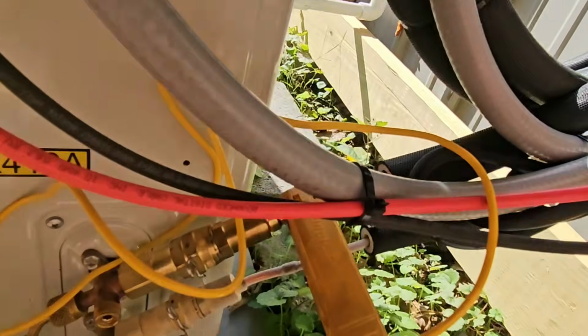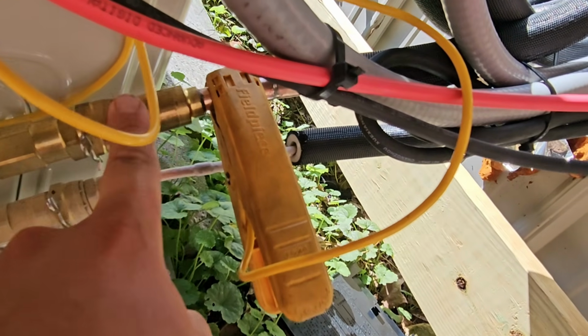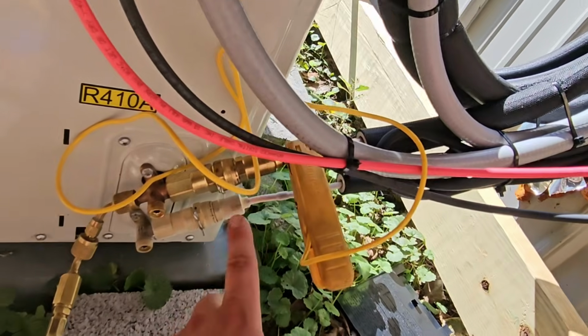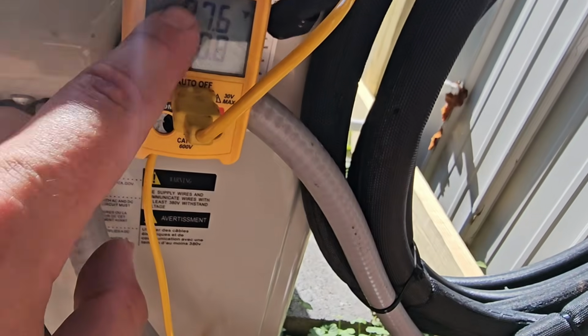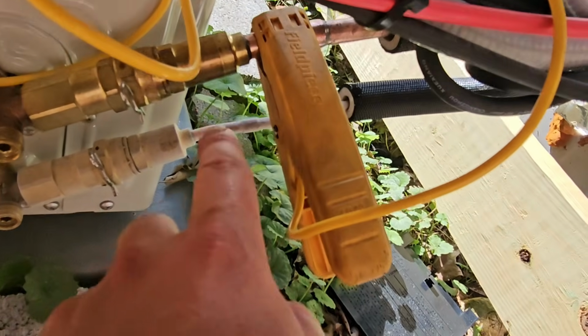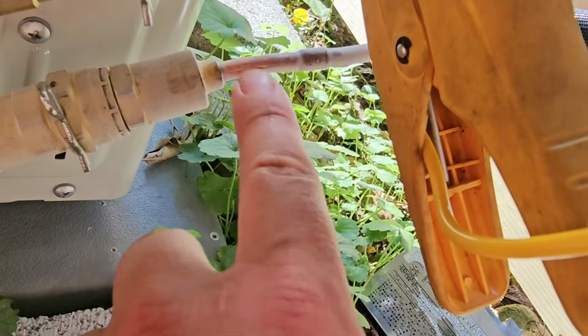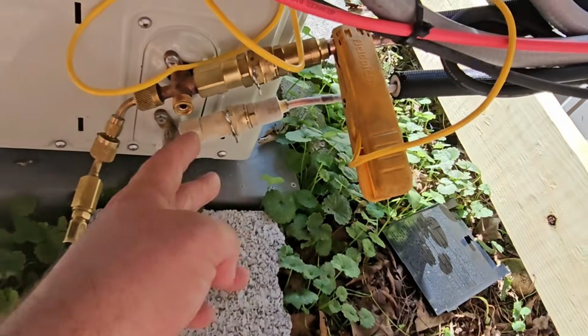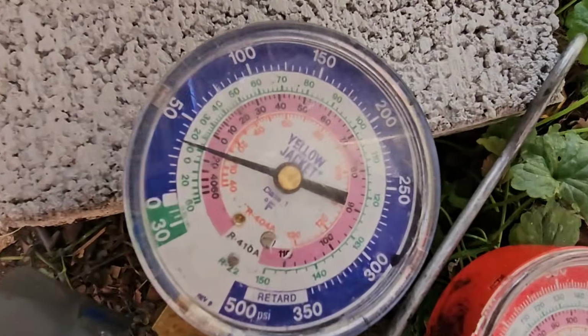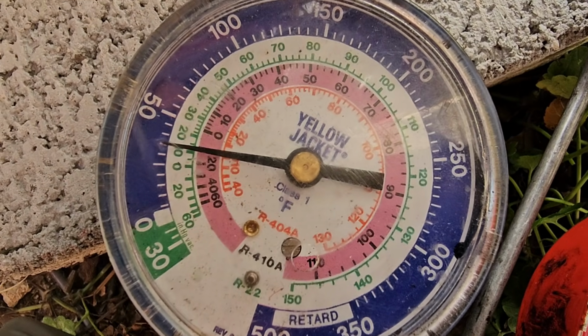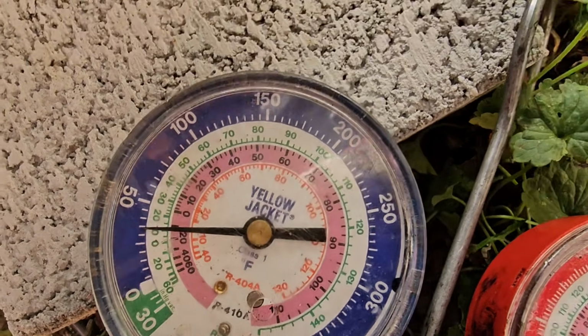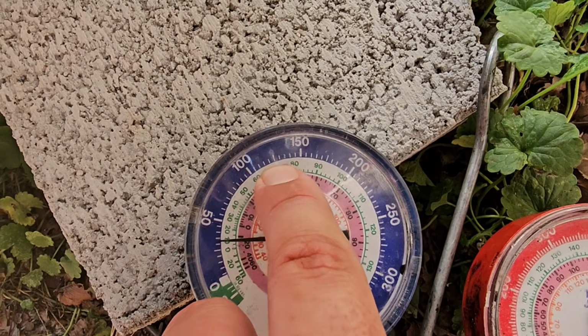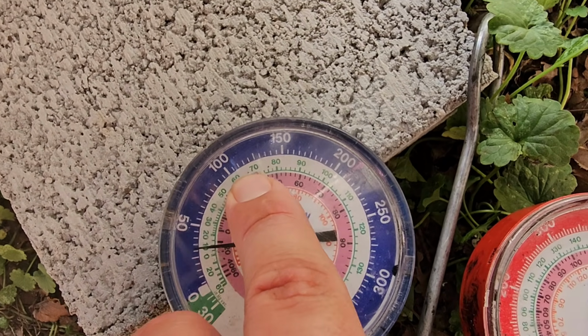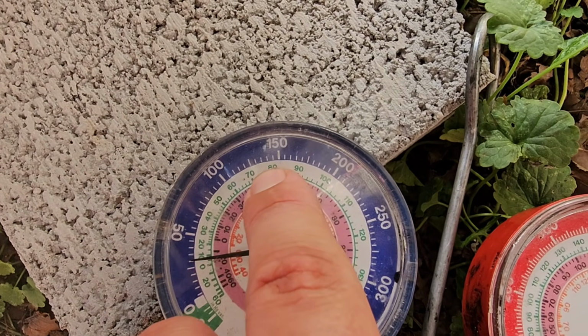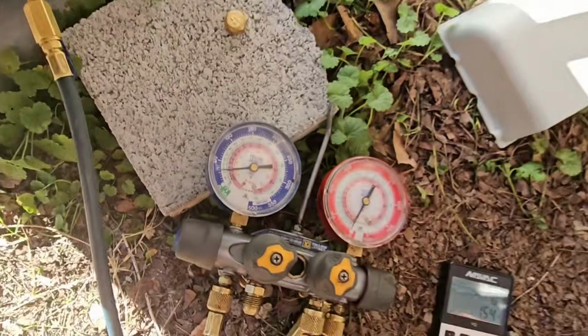And the temperature of this line is an indication of the temperature of the indoor heat exchanger. So if we see 86 here, that means it's probably not blowing out cold air like we want in cooling. But you can see, look at this line, it's freezing up. So that's what happens when you have a low charge on a mini split. Pressure again is 35, right? And on a 95-degree day, with an indoor dry bulb of around 70, 75, it should be upwards of 110, at least 125.